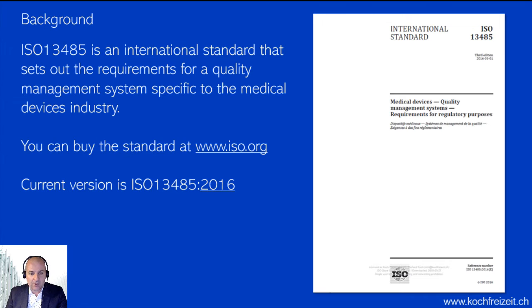So as a bit of background, ISO 13485 is an international standard that sets out the requirements for a quality management system specific to the medical device industry. So you'll see there's a lot of international standards focused on different things. A very common one is 9001, which you may have seen, which is a general quality management system. This is the one you really need if you want to build a medical device.